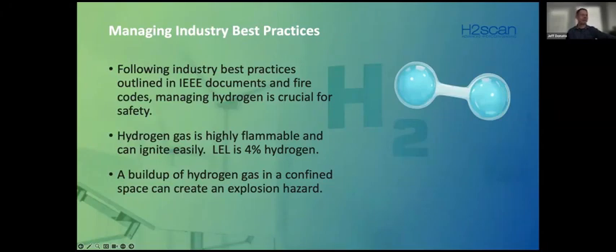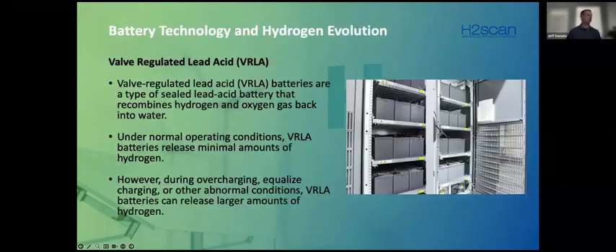And so any kind of buildup of gas that occurs needs to stay below that level. I'm going to show you a couple examples of how things can creep up on us when it comes to batteries. When it comes to utility batteries, we're mainly talking flooded batteries in substations, or what we call vented lead acid batteries. We're seeing some other technologies come out in multiple industries that have different gassing properties, but hydrogen is present in anything considered an aqueous battery. So be it lead acid batteries, or nickel cadmium batteries. I will address the lithium later in the presentation, and how that is also a concern, not necessarily under normal operations, but more abnormal operations.